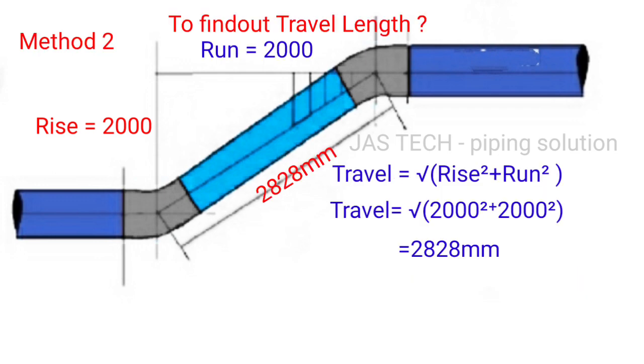Another method to find out travel length. Formula: travel equals the square root of rise squared plus run squared. We know rise and run values are each 2000 mm. So travel equals square root of 2000 squared plus 2000 squared. By using calculator, the result is 2828 mm.